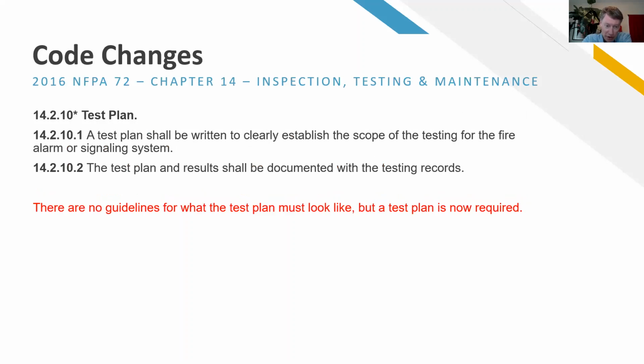This is another thing that affects a lot of our BOMA clients. You should have a test plan to make sure that your critical fire and life safety systems, tied to HVAC and security and elevators and sprinkler systems and carbon monoxide detection, are inspected per Chapter 14 of NFPA 72, 2016 edition. This is part of the code that actually calls out that a test plan and results shall be documented. If you've got a good fire alarm contractor, you might not need to look any farther than the proposed service plan that you're buying from your contractor. This does explicitly require testing and results to be recorded on site.